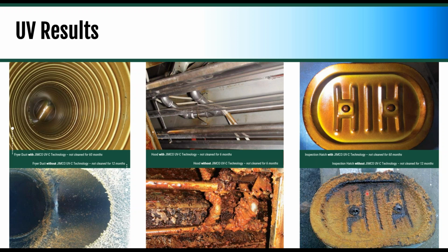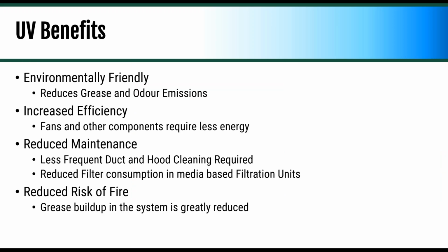Lastly, this is an inspection hatch. This is 60 months and 12 months here. So you can see a very significant reduction in grease deposits inside the hood and ductwork. When we look at the benefits of UV, first and foremost, it's environmentally friendly. It's not a huge part of NFPA 96, but it's getting to be more and more important. And so we really like a product that is reducing grease and odor emissions.